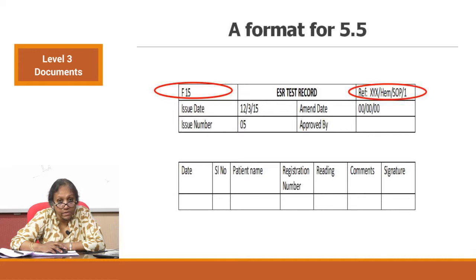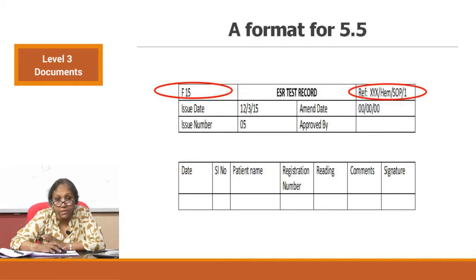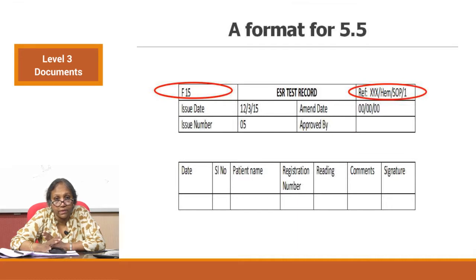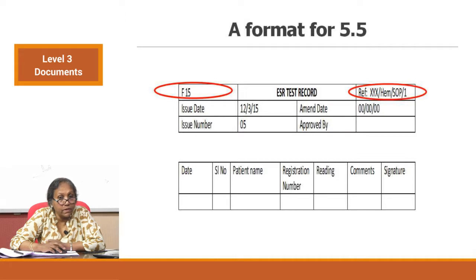For automated assays, printouts serve as records and you keep those. You can make a table listing what you will document. In this example it is a haematology department. For the manual assay format, the ESR test record captures: date, serial number, patient's name, registration number, reading, comments, and signature — that is all. You do not need to complicate it with unnecessary things; the minimum requirement for that activity. This kind of register is in most laboratories for recording patient results. The only additional thing now is to add a document control element.